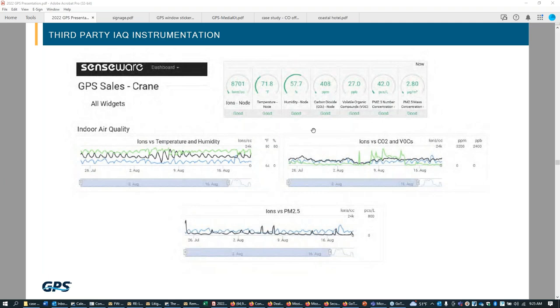What I see as the direction of the industry as it relates to building management, and hopefully design will come along with this too, is that carbon dioxide is not the only measure of indoor air quality. But for over 20 years, the industry has really focused on it because it's a really good proxy for outside air ventilation and occupancy. As occupancy increases, CO2 levels will rise, and outside air ventilation rates are typically designed around occupancy, and we measure occupancy by CO2, and that's fair. A lot of buildings are doing that, and demand control ventilation is one of the more advanced control techniques that I've seen, at least in the properties that I've toured. A lot of them don't even have that, but carbon dioxide is very good to measure ventilation effectiveness and occupancy.